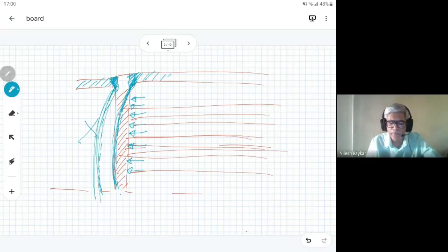There is some strength, or resistance, provided by the tubes. So generally that effect is ignored, because the tube to tube sheet joint is not considered strong enough to hold this particular bending load. So the tube sheet is made thick enough to take this entire load by itself and not induce any load on the tube to tube sheet joint.